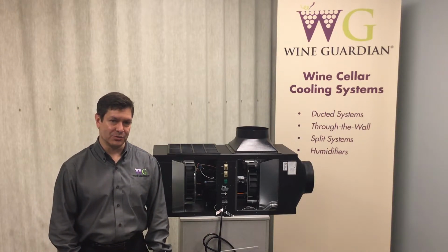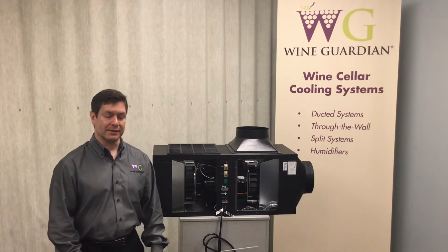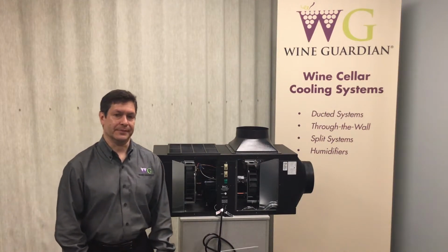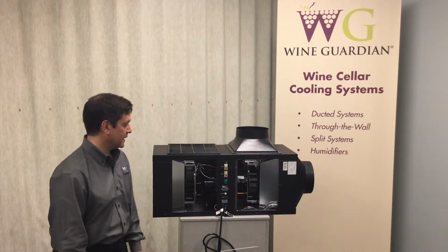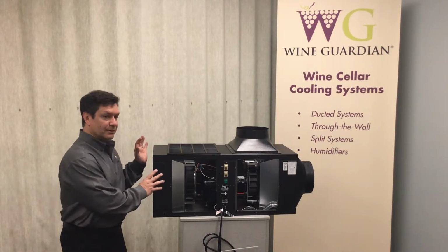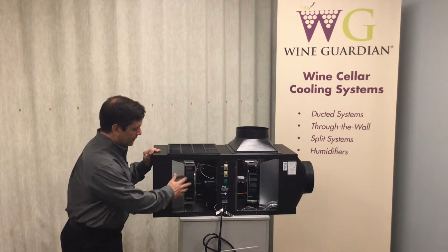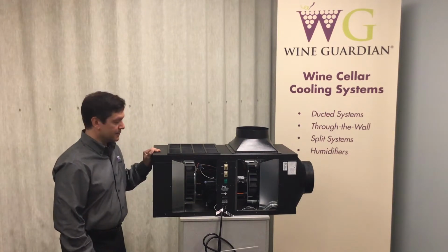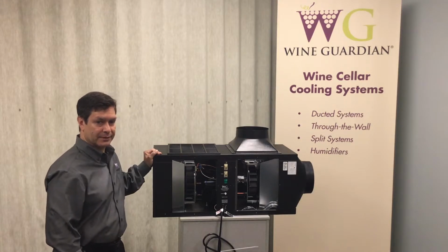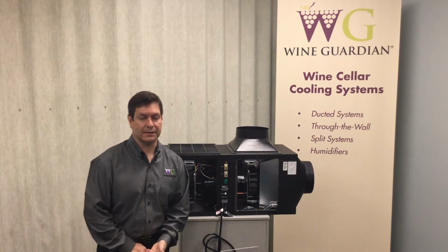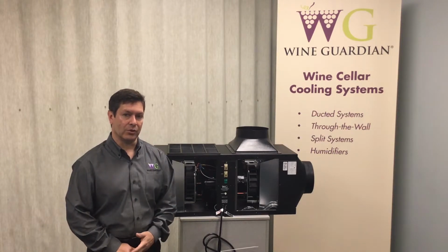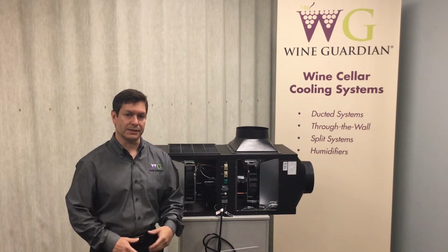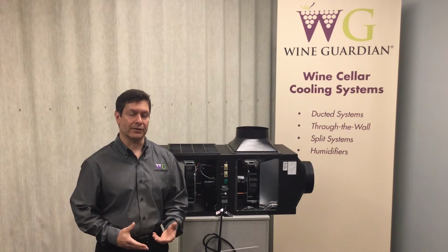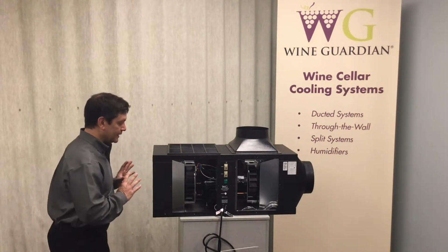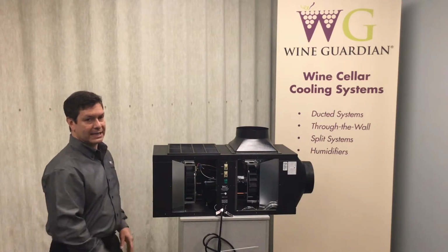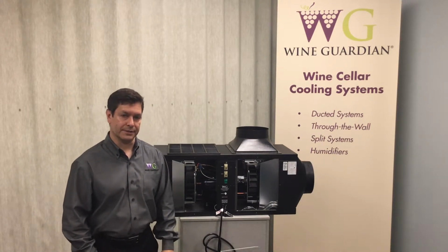Another option that we have that has to do with the ambient conditions that the unit is mounted in is a high ambient version. The high ambient version consists of a larger condenser coil and a larger fan, and that is also a factory option. It's available on our D025 and D050 only. And what it does is it allows the temperature of air coming into the condenser side to be a maximum of 120 degrees Fahrenheit.